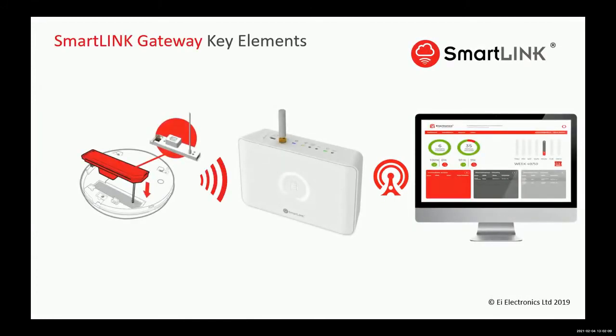So if you look at the SmartLink itself, every unit within the system requires an RF interconnection. So if it's a mains powered unit, it has an RF module in it. If it's a 10-year battery operated unit, it has to have an RF module in it, or we can't download any information from a hardwired interconnect system. We have to do it through RF. The information is sent to the gateway. And the gateway then, as we said earlier, has a roaming SIM, and that SIM will transfer that information to a cloud-based solution. And you can read that information from your desktop on your portal.